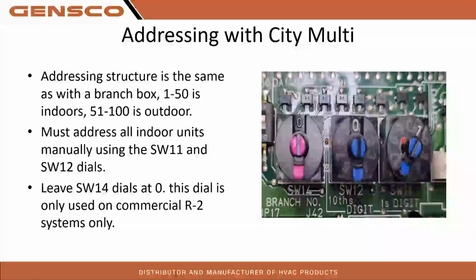Addressing with City Multi equipment is a little bit different though. City Multi equipment, I found, is definitely a lot more sensitive to addressing. If you screw that up, you're going to have problems. So the way it works is the address structure is the exact same. Doesn't matter if you're using City Multi equipment, if you're working on a big R2 commercial job, or with a branch box. Your address structure remains the same. How you set those addresses might be a little bit different though.